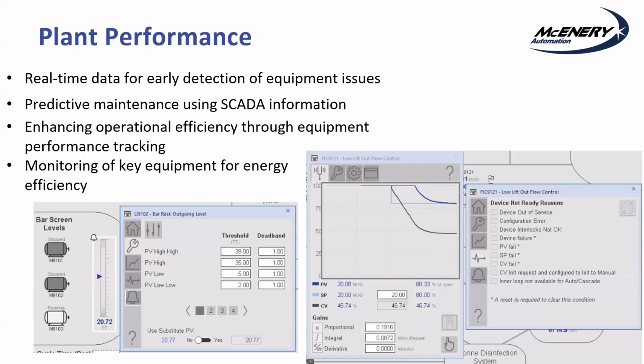What we've done with a lot of our water supply companies is check what time of day it is to compare to peak usage, then build a profile of which pumps - whether on VFDs or motor starters - should be running at a certain time, depending on how big a pressure correction is needed. A low correction could just mean running a small VFD, so we use a little energy instead of hitting it with a pump that's way oversized for the time of day.